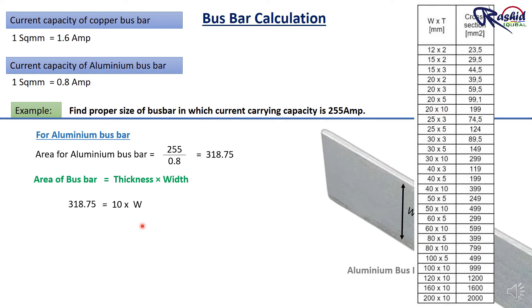Now substituting this value into the formula, we get width of busbar is 31.87 mm. Since 31.87 mm is not a standard size, we can choose the next larger width available in the market, which is 40 mm with a thickness of 10 mm.